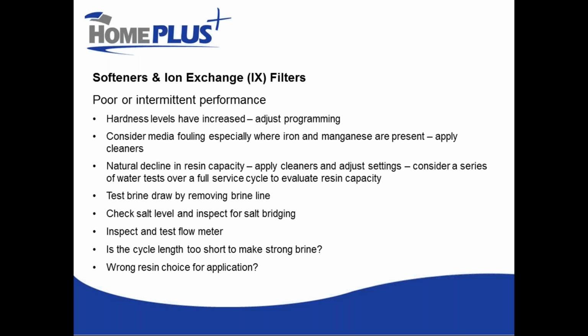It takes time to make good brine as well. So if you've got a very, very short cycle, say you're running twin water softeners, but they're running for 2 hours and then going into regeneration, then flipping over to your other softener, just be aware that you're never going to effectively regenerate because you haven't given enough time for the water to dissolve the salt. So you're using a really weak brine.